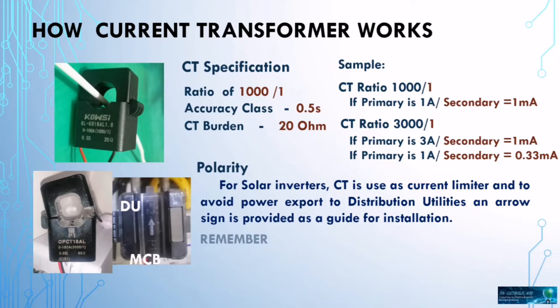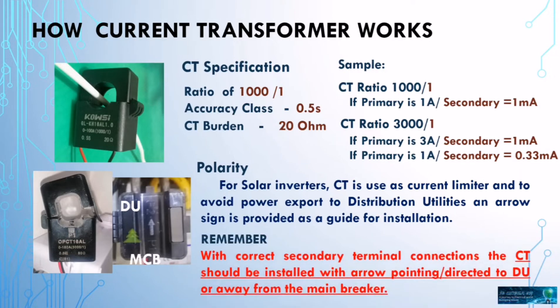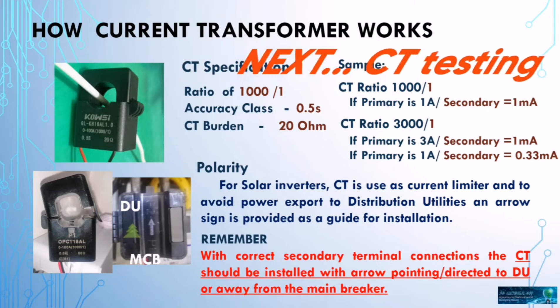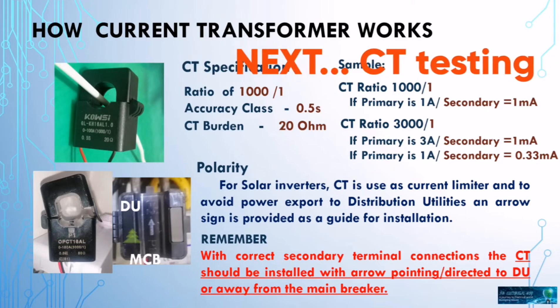Remember, with correct secondary terminal connections, the CT should be installed with the arrow pointing or directed to the DU and away from the load side breaker.